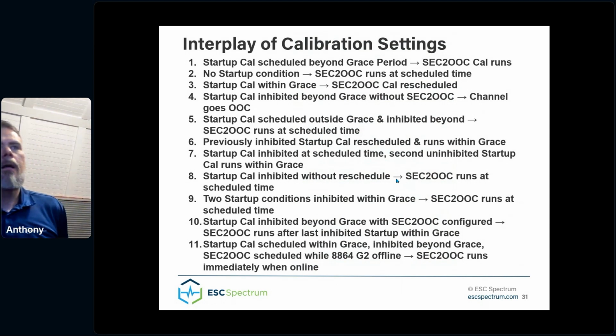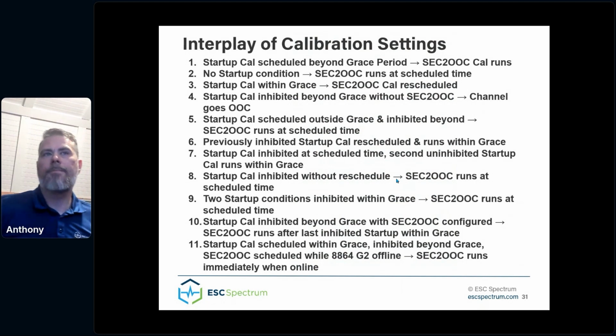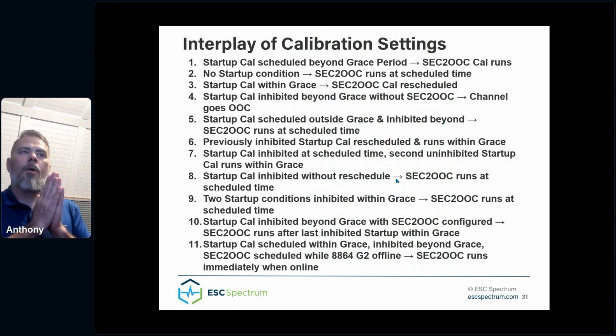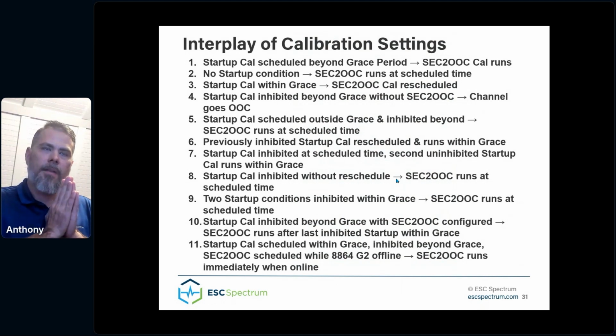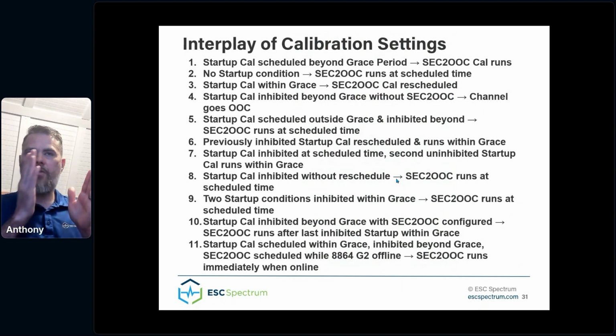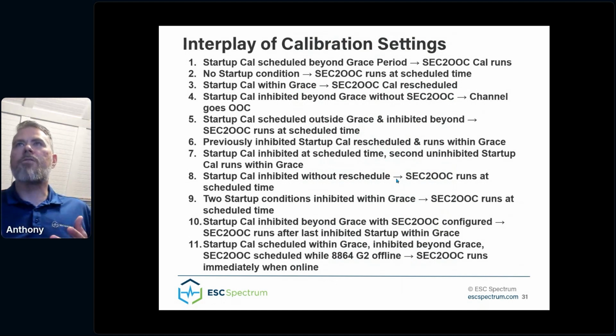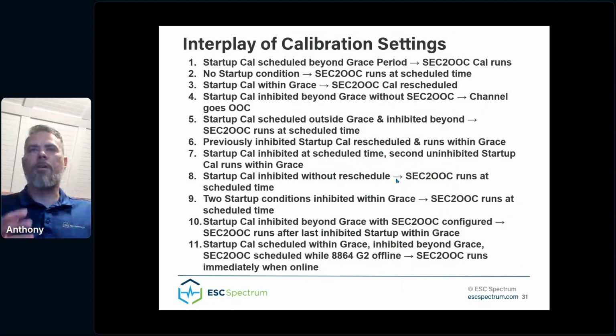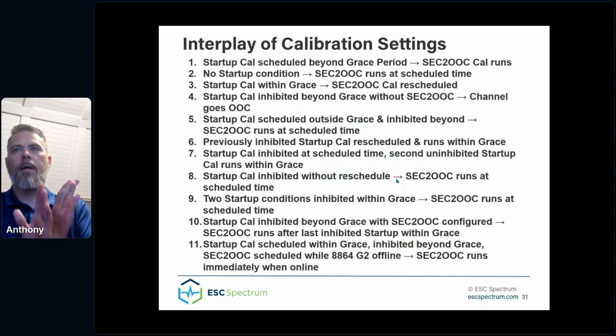Let me give you an example. Suppose you have a startup calibration that's scheduled, but the SEC2OOC calibration is scheduled to happen before that startup calibration. Well, so long as the SEC2OOC value of that channel would not reach 0 before the startup cal would fire, we will wait and let the startup cal happen, which is what we think you would want. You want your startups to happen like they normally do. You don't want to fire off this rescue calibration just because the startup's going to happen. And this is really based off other implementations that the engineers have done in the past using multiple channels and constructs and configurations. And so we set this up to work in a way that they've discovered over the years of doing these other implementations makes the most sense. Because you'll still be in control when that startup cal runs.